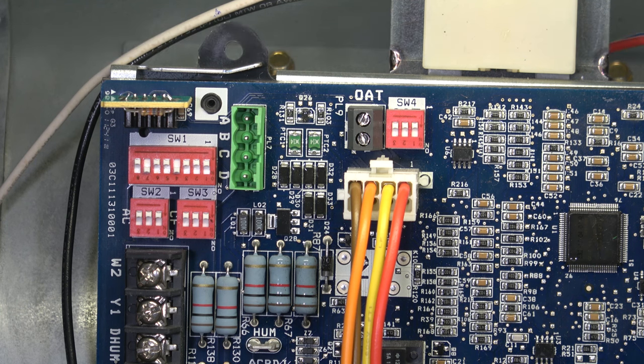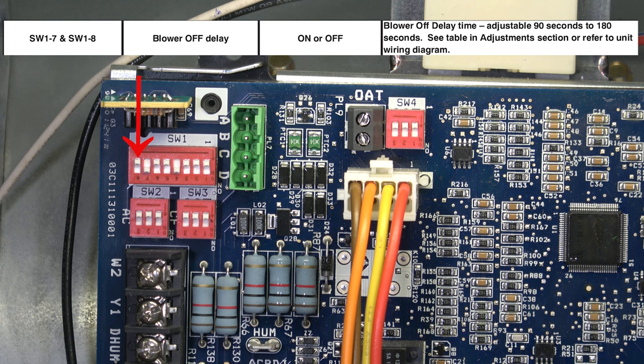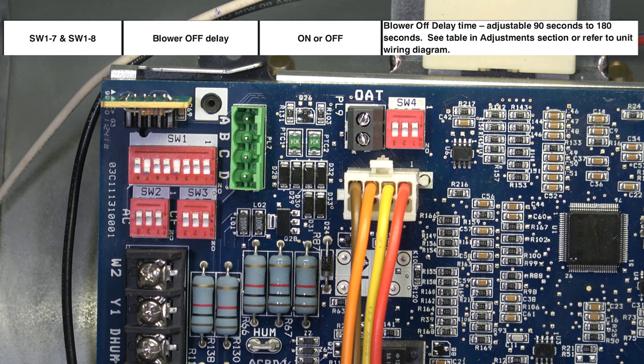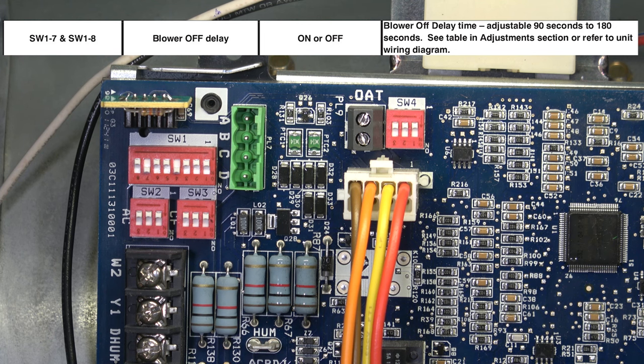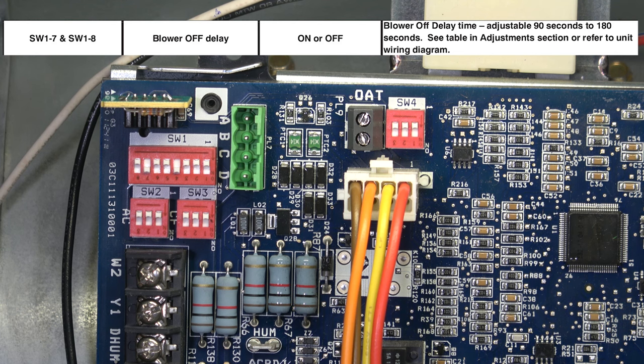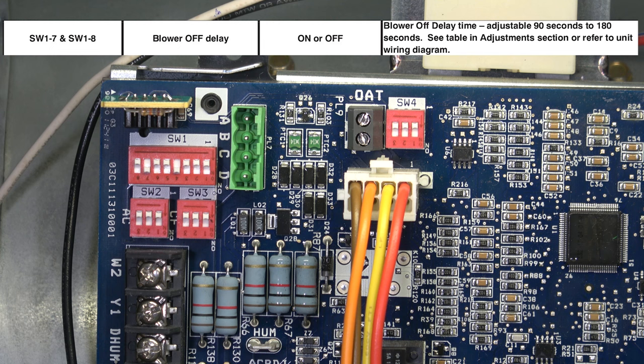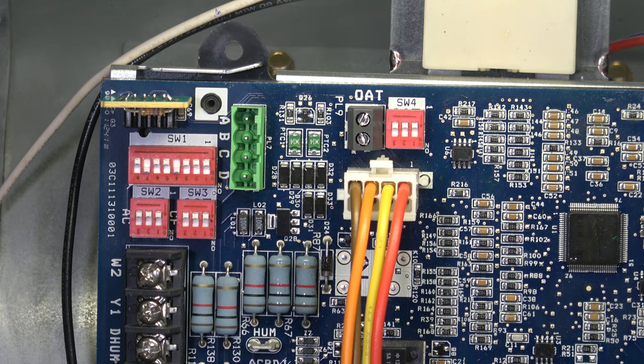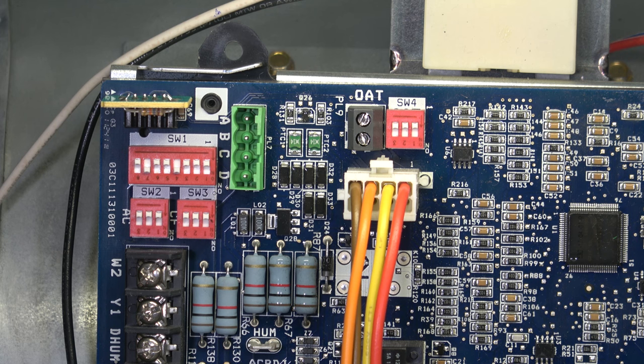Moving to SW1 number seven and SW1 number eight, that's the blower off delay. The combination of how those switches are turned will adjust the timing of the blower off after a cycle between 90 seconds and 180 seconds. For that, refer to the CFM adjustment table to get the specific timing depending on how the switches are set.